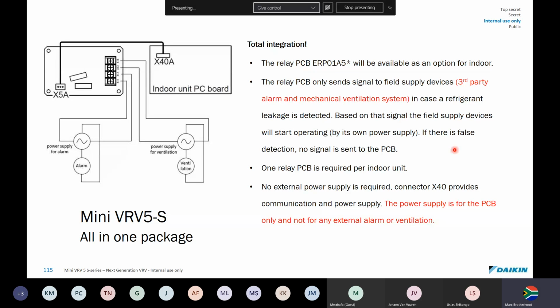This is the PC board we were talking about earlier on that I said I'd get into a bit more detail. The relay PC board ERP 01A5 will be available as an option for indoor units. What this does is it's a relay that sends a signal to field supply devices like a third-party alarm or a mechanical ventilation system in case there is a leak detected.